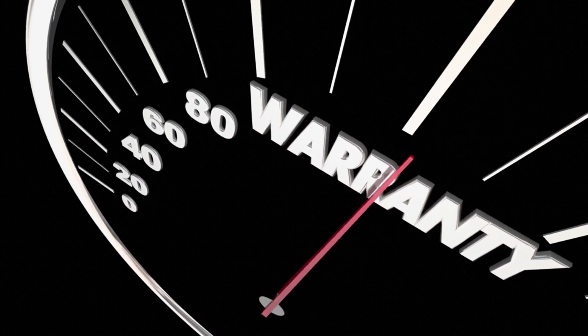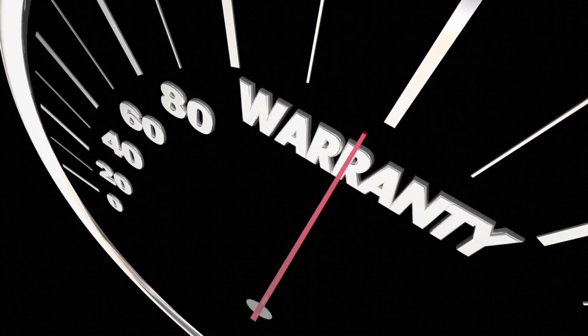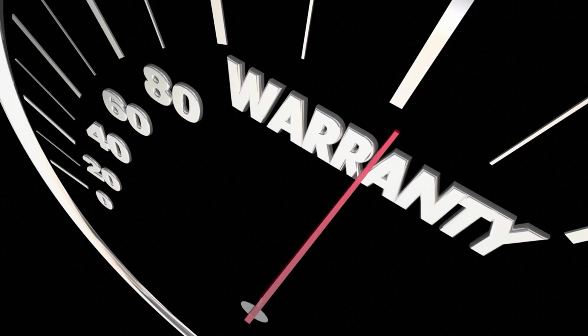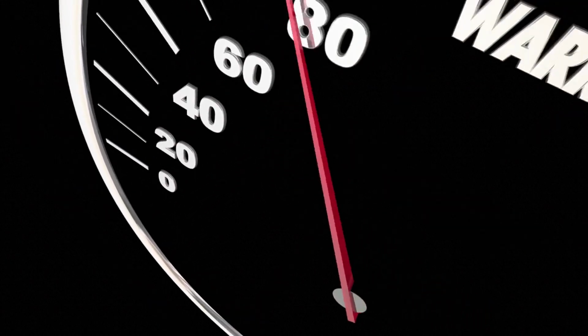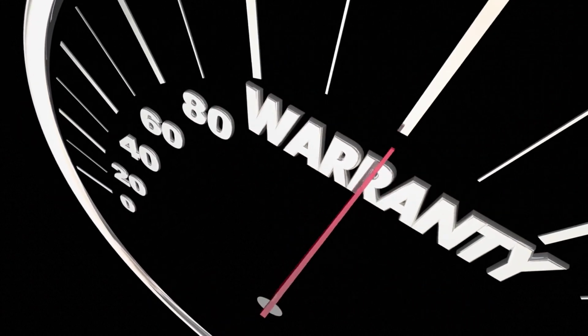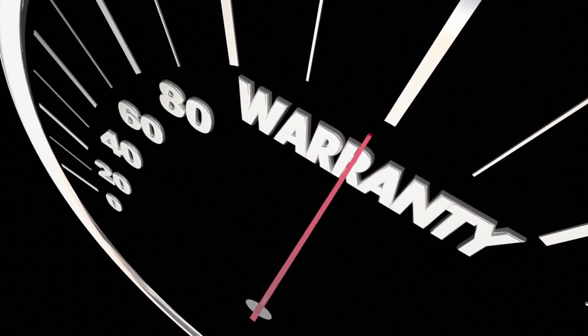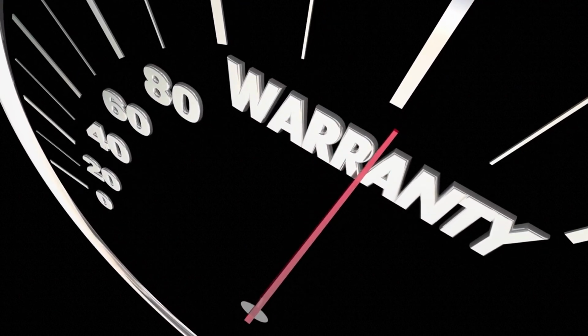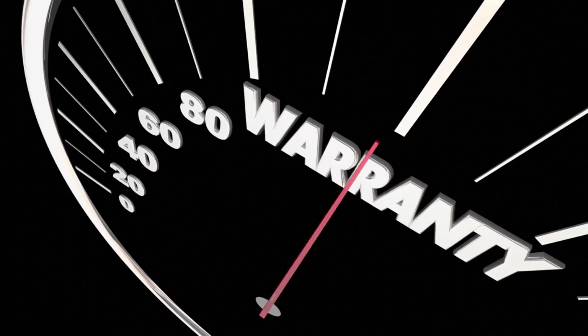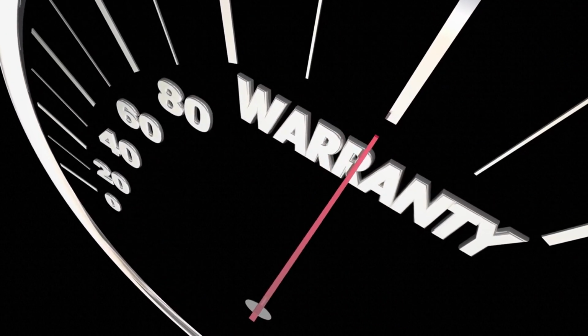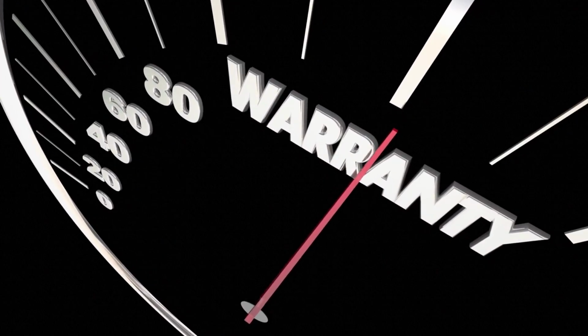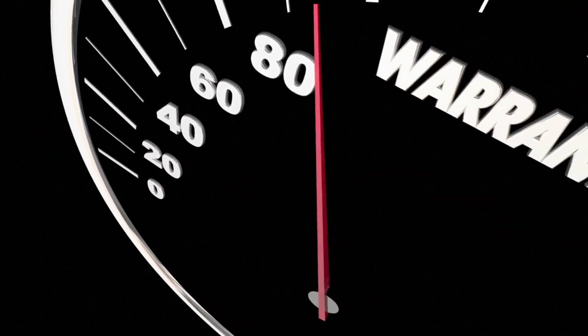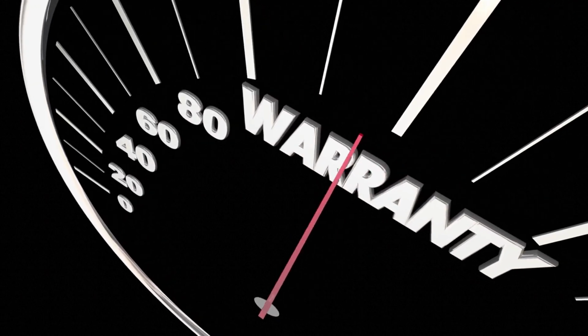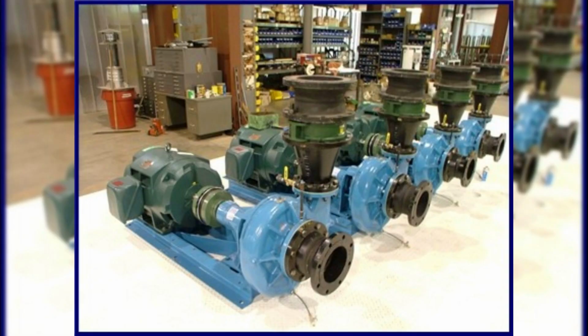For warranties, packaged pumps must be covered for at least 24 months, including both parts and labor. Variable frequency drives, or VFDs, need an even longer warranty, 36 months, again covering parts and labor. The warranty period starts at substantial completion and must include on-site service, replacement parts, and travel costs. This way, DOE facilities can count on reliable support during the early stages of operation, when dependable performance is most critical. Let's talk about the pump types and materials.